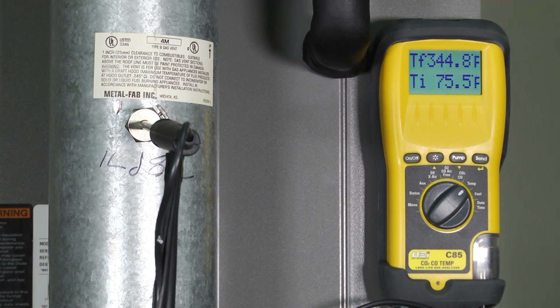When we look at the AHRI standard for carbon monoxide, we can actually have over 200 parts per million in the flue gases and it's considered acceptable. The thing to remember is that at Lennox, we really want nothing more than 50 parts per million. So we want to make sure our system is below 50 parts per million, and if it's not, we want to know why. And when we talk about that 50 parts per million, it's what we call air-free. And that's really about understanding what air-free is.